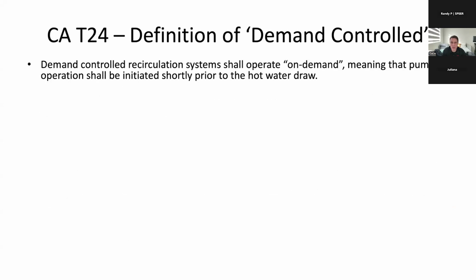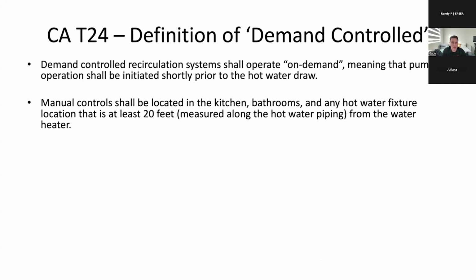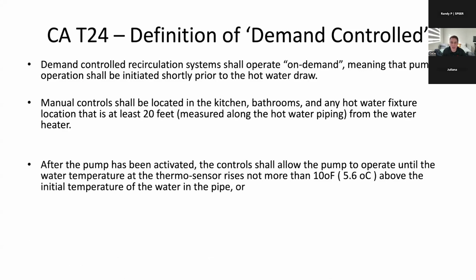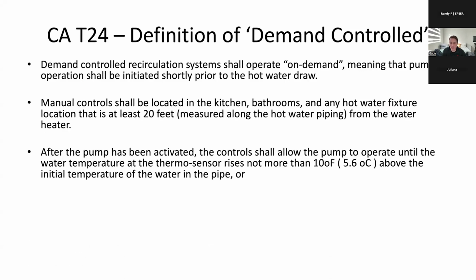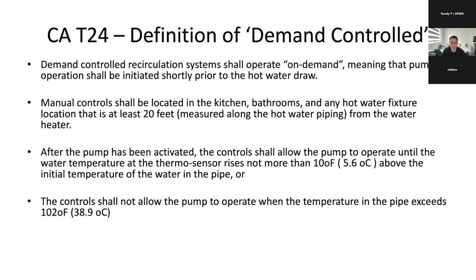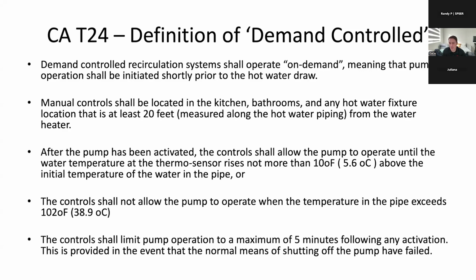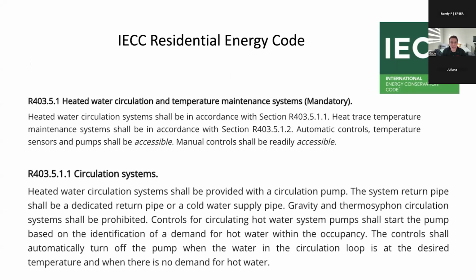But they do go into some pretty good definition of what it means. The pump shall operate initially shortly before the hot water draw, and manual control shall be located in the kitchen, bathroom, or any hot water fixture that's at least 20 feet from the water heater. And then same language as before about sensing the rise in temperature, so either a 10-degree rise or a 105-degree lockout, and then the 5-minute timed lockout for protecting the pump. Okay, IECC.